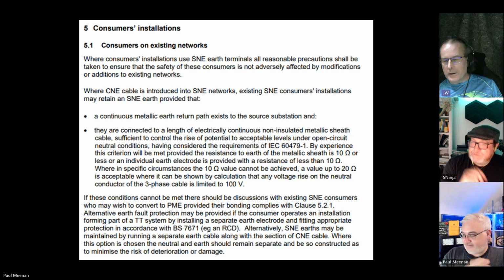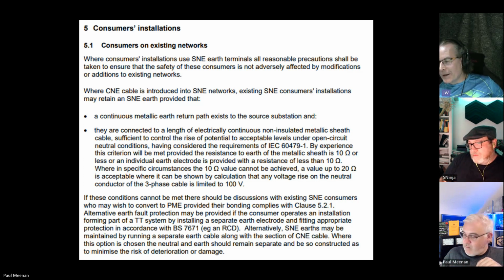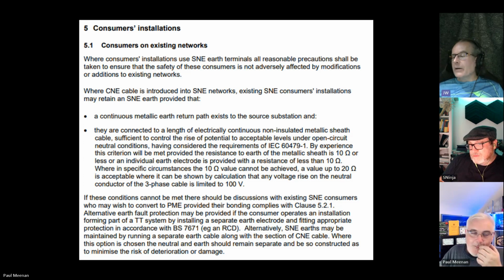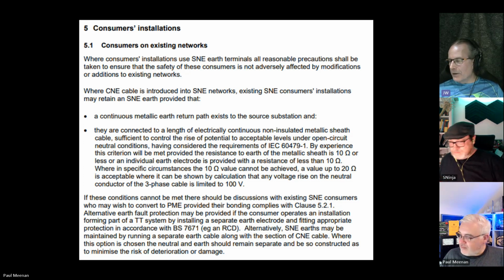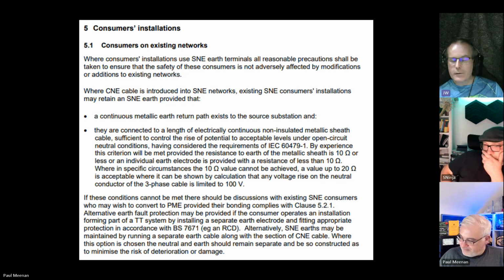Yeah, the problem is that, as it says there, that 10 ohms is from experience. So in other words, what they've done before. And the thing about the calculation is that it's impossible, because how are you going to calculate it on an existing network that's got bits of it installed all over the place, hundreds of meters of goodness knows what installed under the roads and been there for 100 years and all the rest. If you're designing a new one, great, you can do all the calculations. But for any existing stuff, calculations are out the door because you just don't have the data for what's installed. So it's essentially saying, because we've done all this before for years, we know that in most cases 10 ohms or less is probably going to be safe.